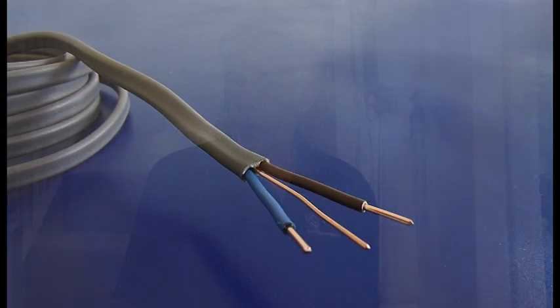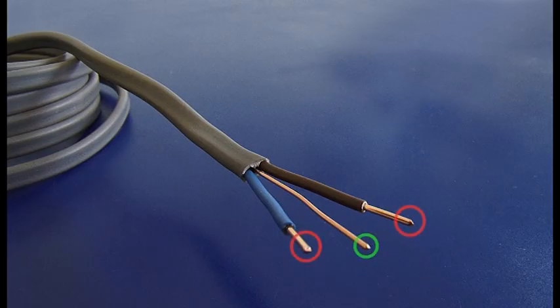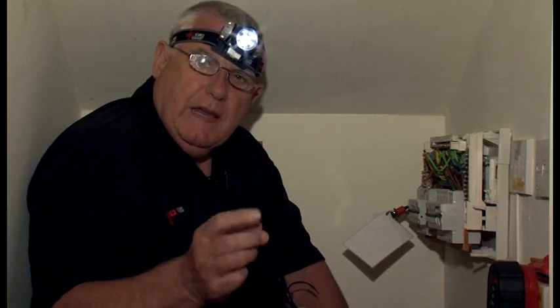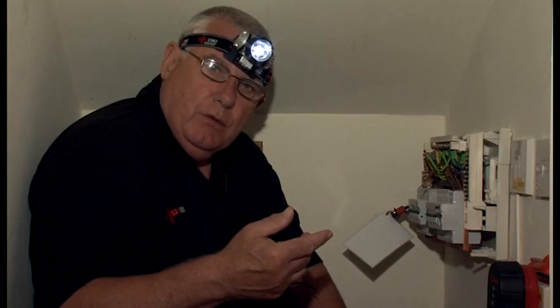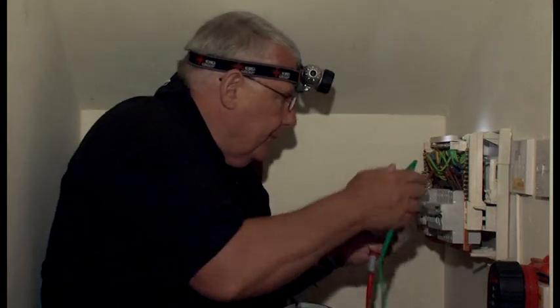Finally, Tony will move on to measuring between each of the CPCs. Now, with twin and earth cable, it's important to remember that the CPC, in many cases, will have a smaller cross-sectional area than the live conductors. The most commonly used twin and earth for a ring circuit has 2.5mm squared live conductors and a 1.5mm squared CPC. And proportionally, this is about 1.67 times smaller than the live conductors, so should have a resistance 1.67 times higher. Now, as Dave said, 1.67 times the line conductors. Now my line conductors were 0.72 of an ohm, so I'm looking for a reading in the region of about 1.2 ohms. So let's see what we get.